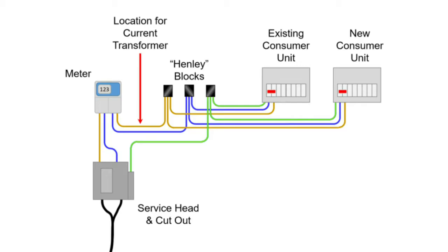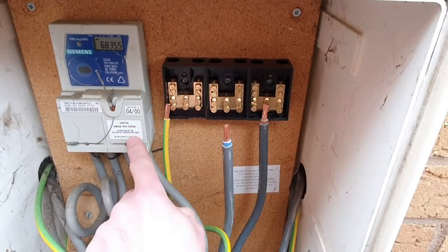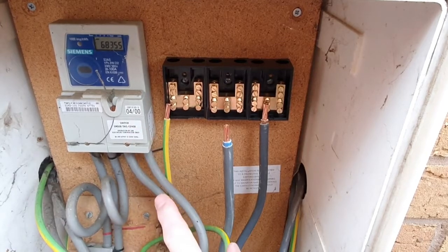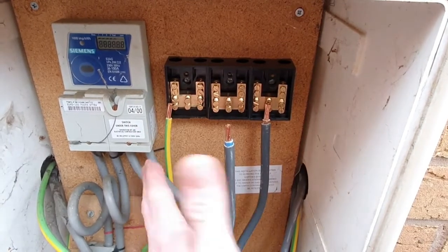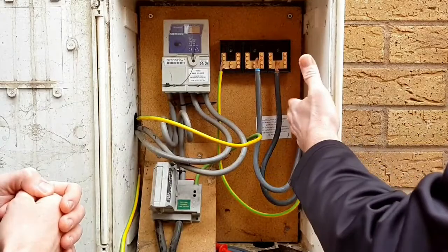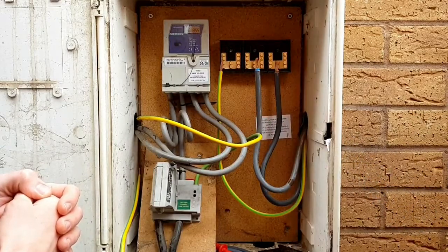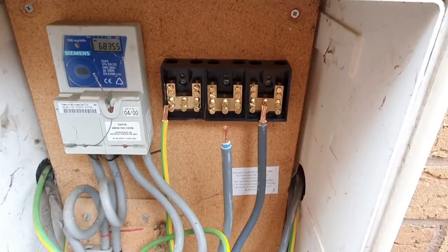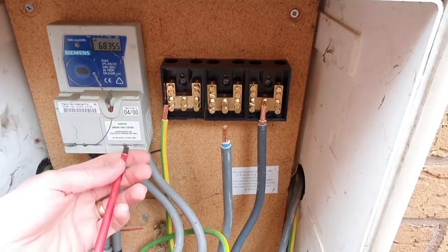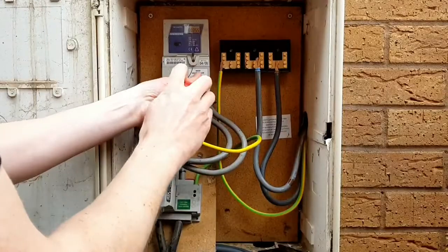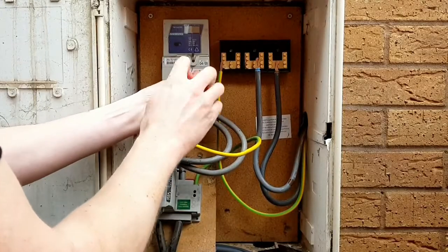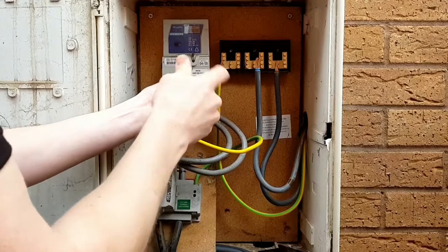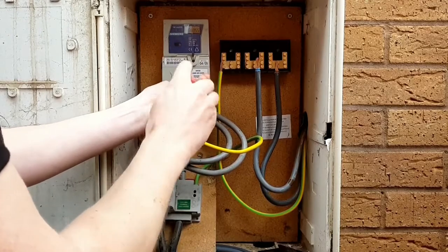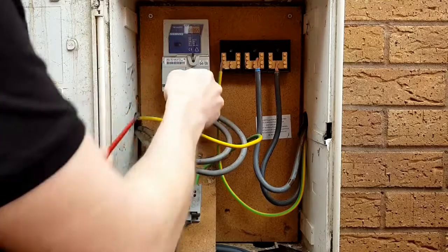I think first of all, we're going to actually take this cover off. We'll be very careful here. Take this cover off. We're going to isolate it using the switch, and then we're going to prove it's dead, and then we can start looking at these connections and working out which one that CT meter is going to go on. Okay, so the first thing we're going to do is we're going to remove this cover here. I must have undone hundreds of these in my time. So just undo this little front cover, and that allows us to access the isolator switch.